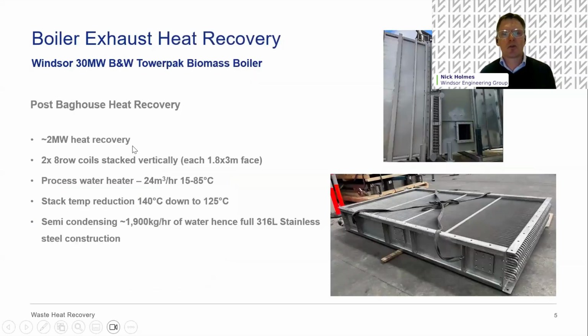So there's 3 or 4 specific case studies here just to give an overview. Typically, economizers are used in boilers, and have been for a long time, but they're limited in how much heat you can recover because they're preheating your feed water. So the feed water temperature and the flue temperature get to a similar balance. You can't drop the exhaust temperature any lower. But with an additional heat recovery coil, heating an alternative heat sink, you can drop your flue gases significantly lower.